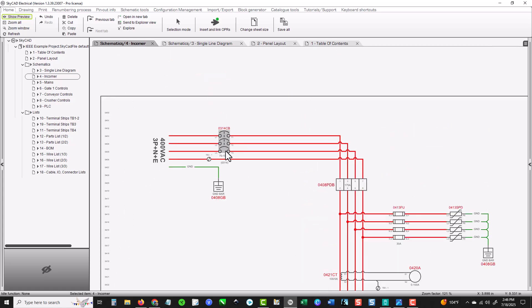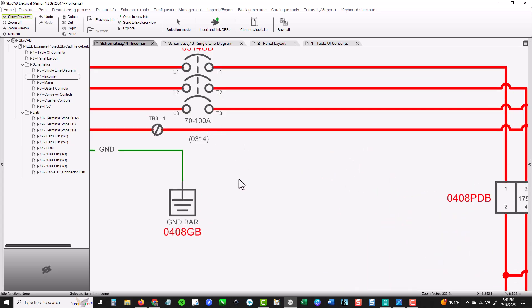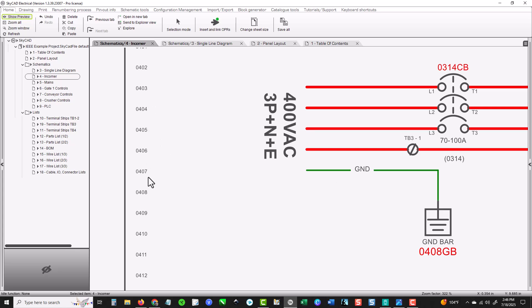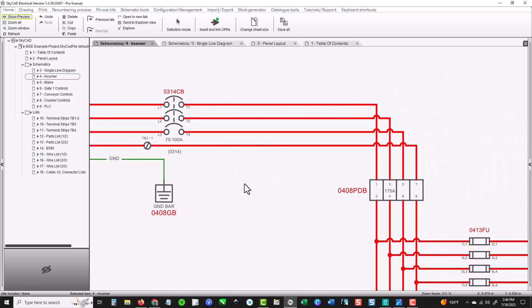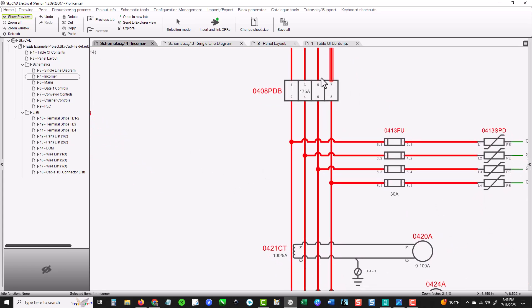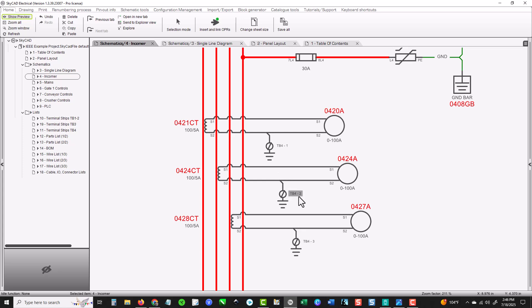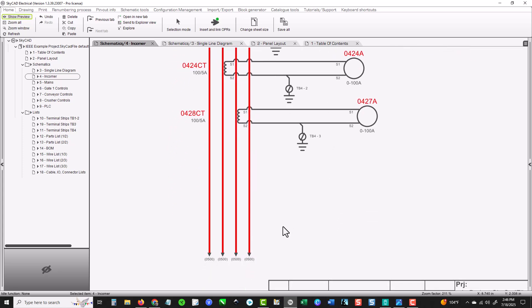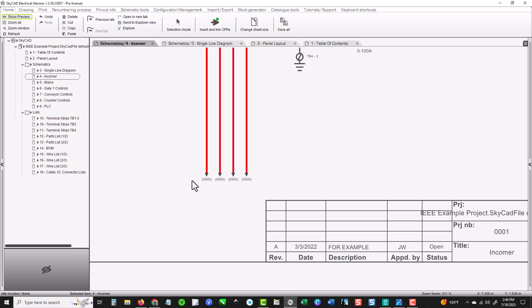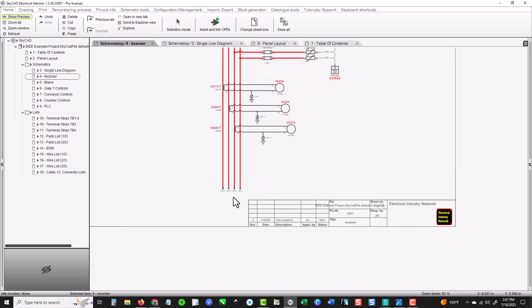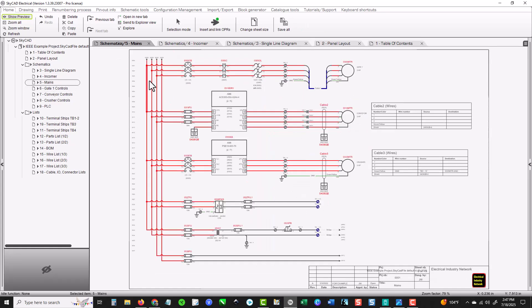Here's our power coming in — three phase and neutral — with your main circuit breaker. Down here it gives you the rating of the circuit breaker. These are rung numbers; your rung numbers give you a location of where everything is. Here's that power distribution block I showed you earlier. Look at these connection points — the dots are line jumpers. You've got a fuse block, a surge protector, and your amp meters which I showed you on the front panel.